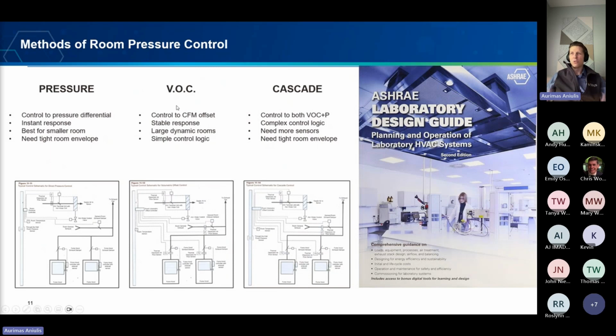Most of the time, VOC is most commonly used because that's probably the easiest cookie cutter approach to room pressure controls. And it's great for large spaces where there's a lot of traffic, a lot of doorways, a lot of fume hoods. Any dynamic air disturbances, VOC is going to be a better way to respond to prevent nuisance alarms. Direct pressure control is great for small, tight spaces like ORs and patient isolation rooms, where it's super critical to know if there's any change in containment instantly. So any alarms in a pressure control room should be taken seriously immediately. VOC nuisance alarms are typical because they didn't close the door, or they're standing in the door open and the timers trip out and cause a nuisance alarm like, hey, close the door, it's not safe.